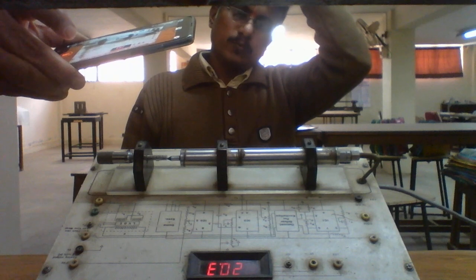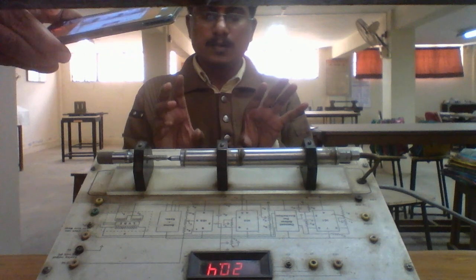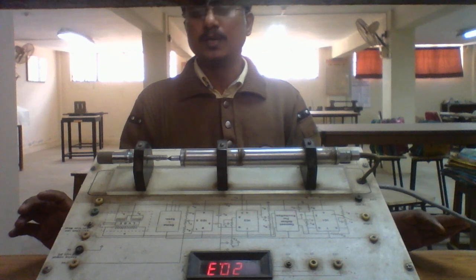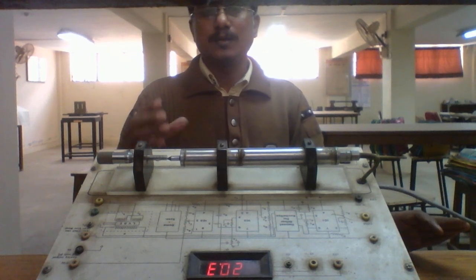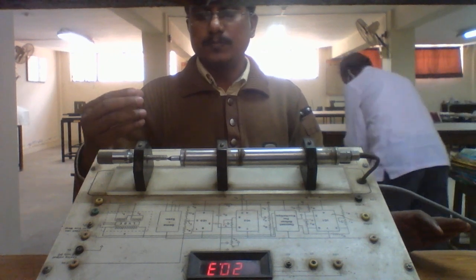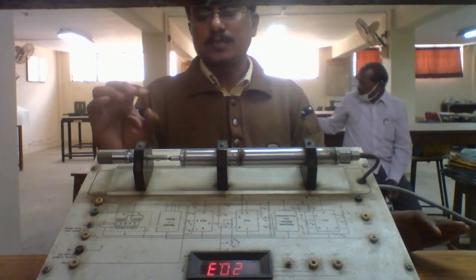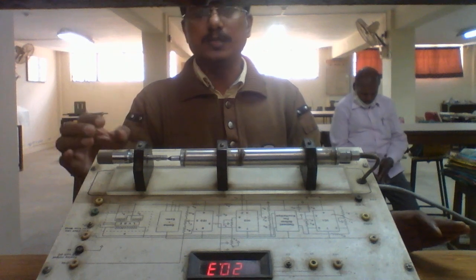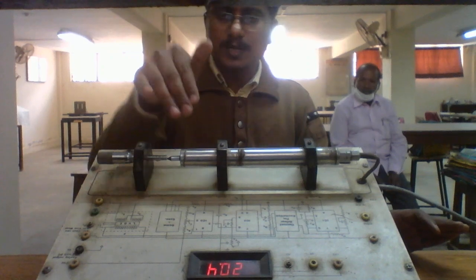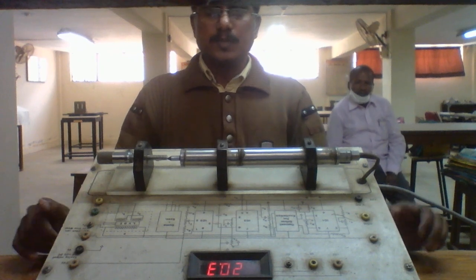The readings we are observing are more than what we displaced. These results are due to systematic errors. These errors are because of system wear and tear. Because of continuous use, certain wear and tear of the instrument occurs, and that may lead to systematic error, and we are seeing that reflected in the output. That is 20.3.